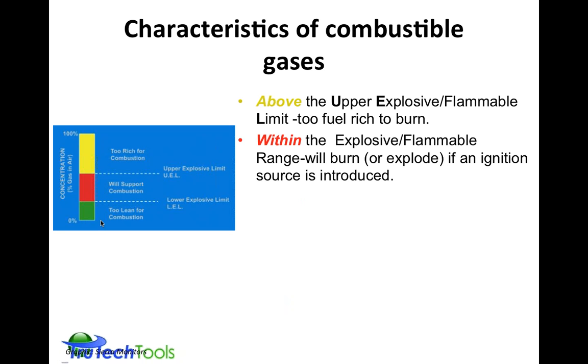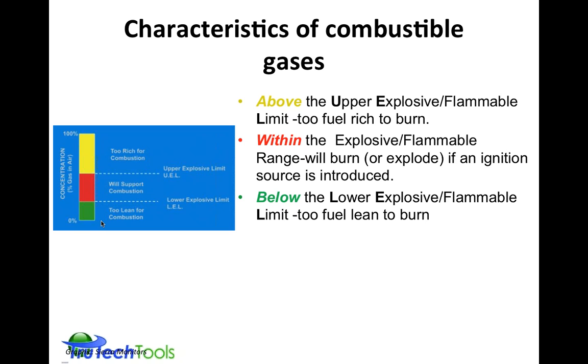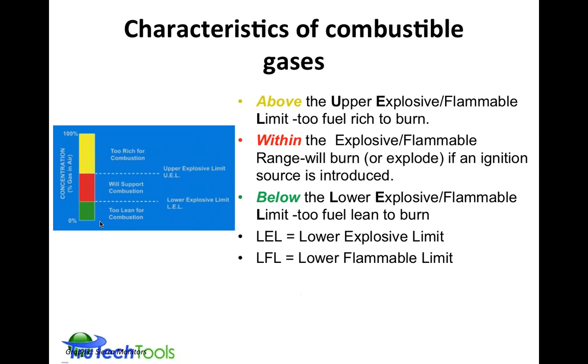Red, within the explosive and flammable range, there's correct concentrations of air to oxygen that a source of ignition, once introduced, could cause an explosive combustion. In the green zone below the LEL, or sometimes it's also called LFL, lower flammable limit, it's too lean to burn. There's not enough fuel present for the oxygen. And basically LEL and lower flammable limit are equivalent terms, but most of the time you're going to hear the term LEL, lower explosive limit.